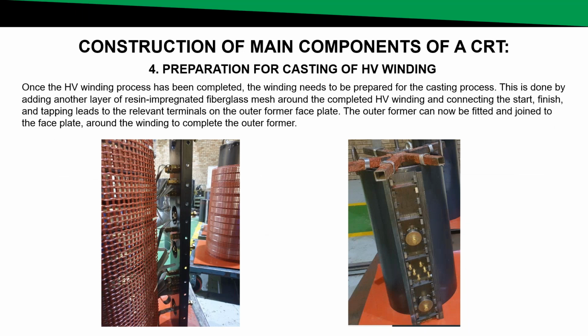So after the HV winding has been completed, this HV winding now needs to be prepared for the casting process. This is done by adding another layer of resin impregnated fiberglass mesh around the HV winding. And then all the connections, the start, the finish, the tappings, need to be connected to the outer former faceplate. Once all the connections have been completed, the outer former can now be fitted around the HV winding and joined to the faceplate of the outer former.